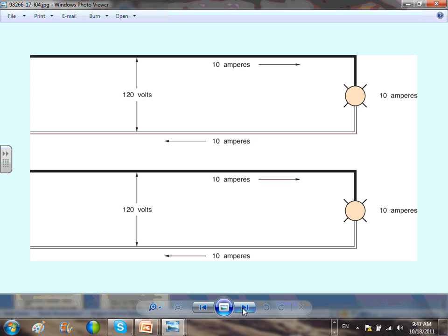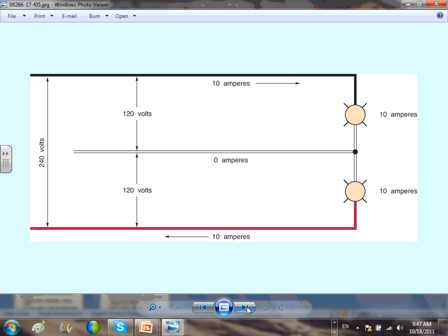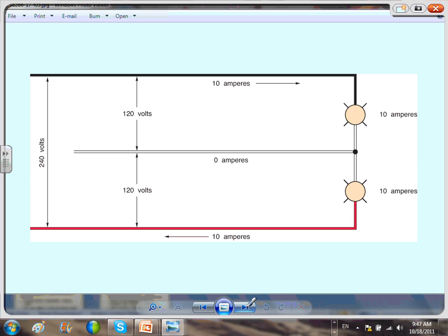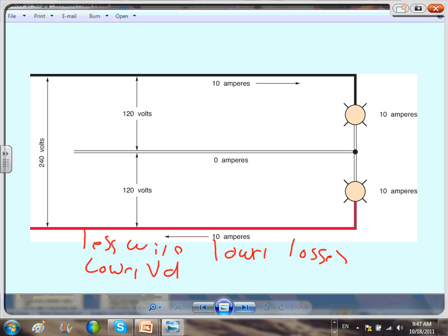Do I have shared neutral? What's a multi-wire branch circuit? Shared neutral. Then up to this point, as you can tell, is this a multi-wire branch circuit? No, it's not a multi-wire branch circuit. Now, is this a multi-wire branch circuit? Yes. Why do I save? So if you guys look at what they did, we saved, so less wire, and lower voltage drop, and also lower losses. These are the advantages of a multi-wire branch circuit.